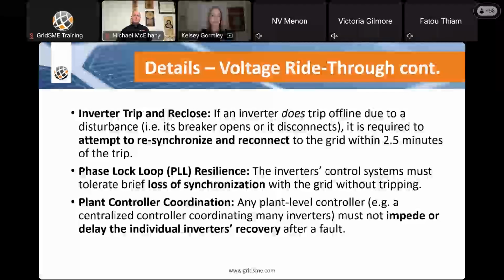Appendix H requires that plant controllers be programmed to allow the inverters to promptly resynchronize and ramp up power immediately following that fault clearance. Only after the inverters have resumed normal output should that plant controller resume its higher level control actions. This helps to ensure that the ride-through and rapid recovery behavior mandated by Appendix H is not overridden by a slower plant level control scheme. So with Appendix H, you've got to hit it no matter what your plant controller is doing.